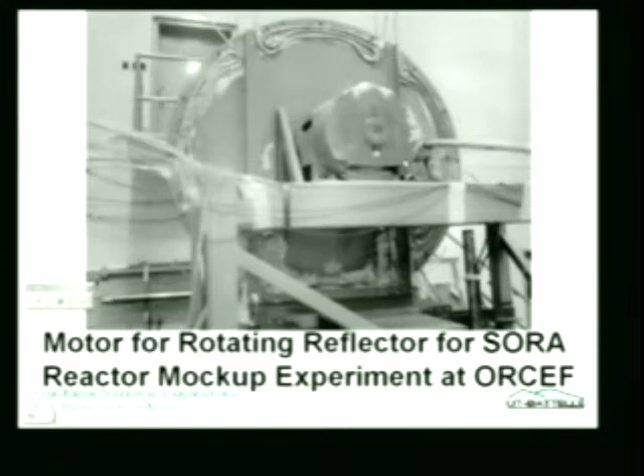What happens with this 75 horsepower motor is it kind of loads your electrical system down. And this Cockcroft-Walton accelerator had something called a Penning ion source that we were pulsing on just for a few microseconds. What this motor was doing was that every 960 revolutions, it missed one. It didn't keep up with the 60 cycle because of the load. So instead of getting 960 in a certain time period, we got 959.